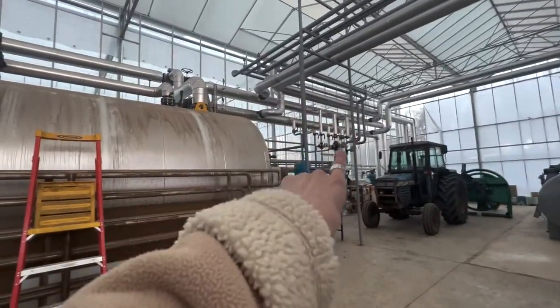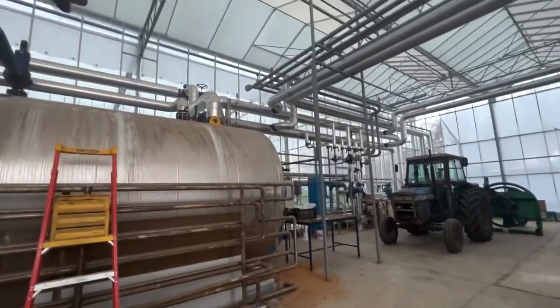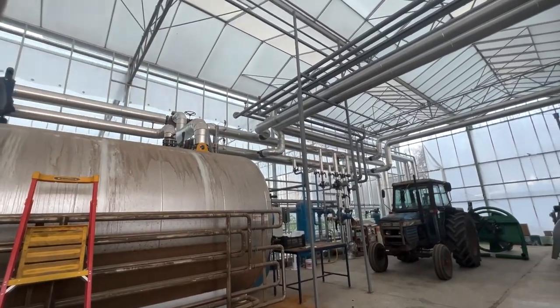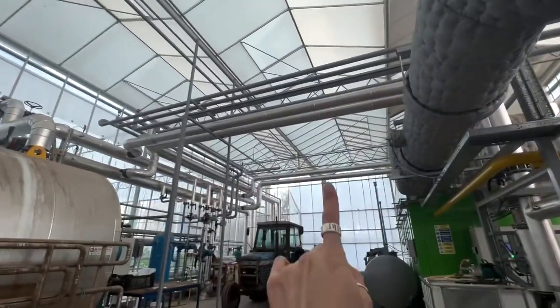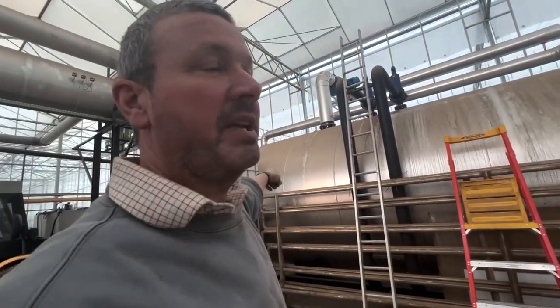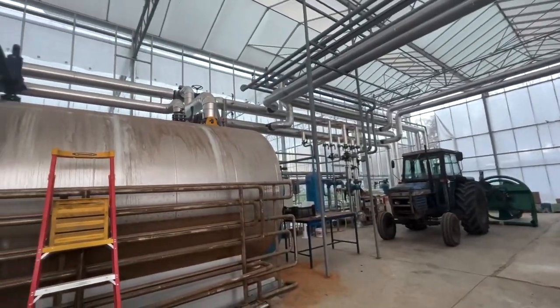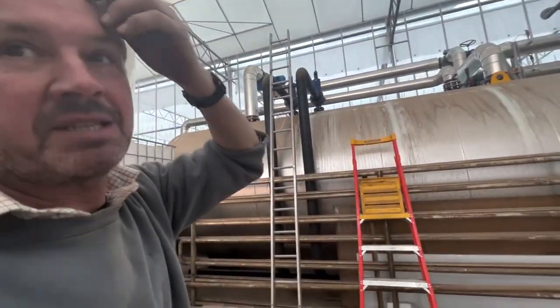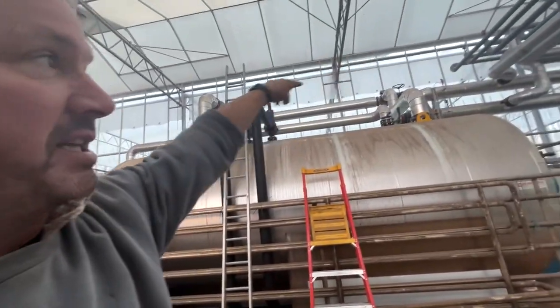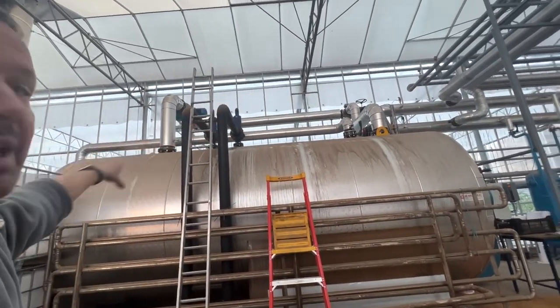What's all this over here - to do with the boiler? Yeah - just flow and return mains to the tank. Those two go up across to the other side. And then you get the low-grade heat from the condenser, and this goes into the grow tubes - 40°C max. The high-grade heat goes into the tank, stored, and you use it from the tank in the greenhouse. That's your really big tank over there.